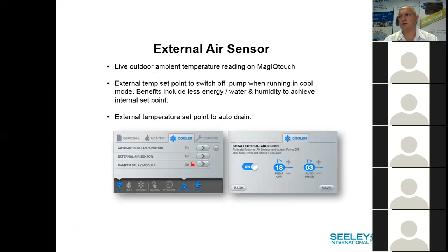The external temperature set point to auto drain. In certain areas where you have freezing temperatures, and especially extreme temperature divisions, what will happen is if it gets to a point where the water starts to freeze, and you can set that temperature. So if the temperature gets to 3 degrees, that's external temperature, it'll automatically drain, switch off the pump, of course. Naturally, your cooler is probably not going to be on anyway, but it'll automatically drain the cooler to get the water away from the pipe and from the pump and all this kind of stuff, as you've seen in certain cases in America where even toilets are freezing up.